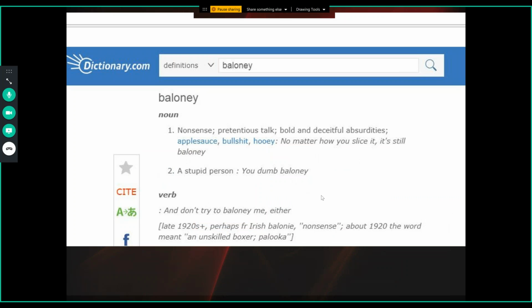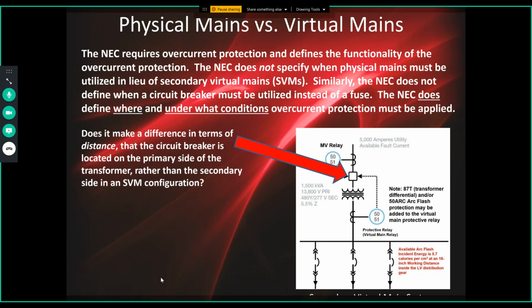People who have seen this slide before have said, I've heard authorities having jurisdiction actually challenge me that secondary virtual mains are not approved by the National Electric Code. And my answer to that is baloney. That is not true. A secondary virtual main is not defined one way or the other by the NEC, any more than the NEC defines that you have to use a circuit breaker or a fuse. Let's be clear, the National Electric Code requires overcurrent protection and defines the functionality of the overcurrent protection. It does not specify when physical mains must be utilized or secondary virtual mains. You can use either.